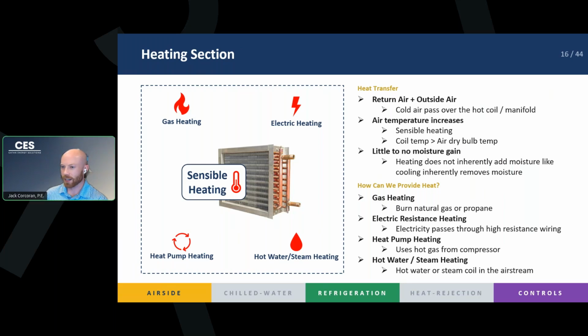You'll hear terms like packaged rooftop unit with direct fired gas heating or packaged rooftop unit with heat pump heating. You know, it depends, or like electric heating, electric cooling. So you'll hear that the heating section often defines the type of rooftop unit that you use. And because it's so flexible, you have different options. Our gas heating is usually our propane or our natural gas. Electrical heating just uses a resistance heat coil, right? It's just one-to-one electric heat, or we can use heat pump heating, running our refrigeration cycle in reverse. In that case, you actually don't have a different heating coil. You would have the same DX coil just operate in reverse.